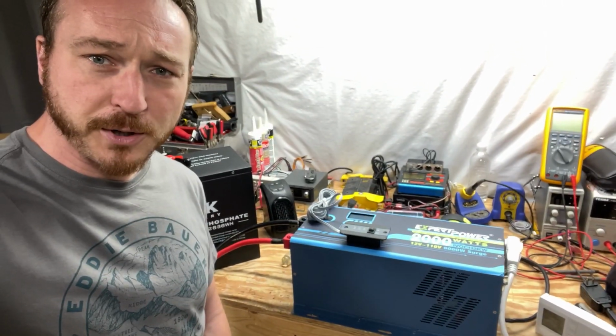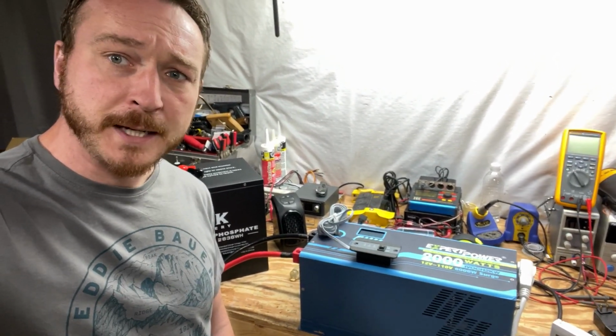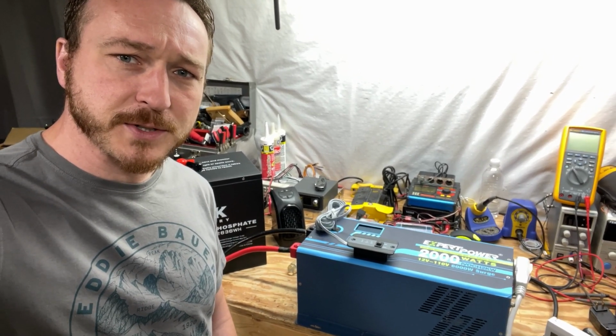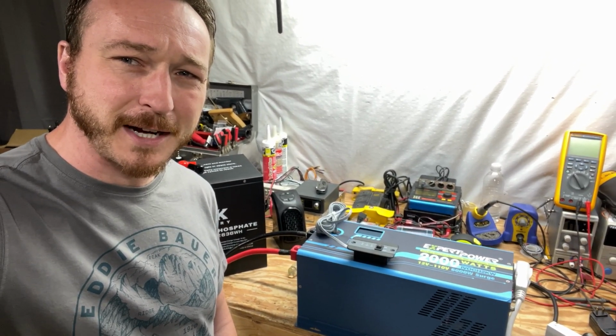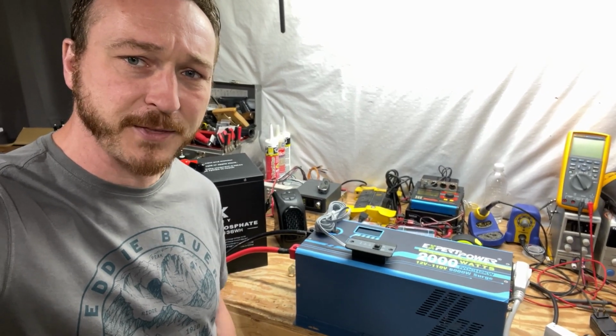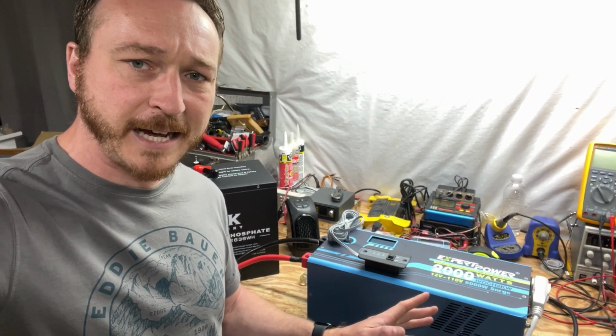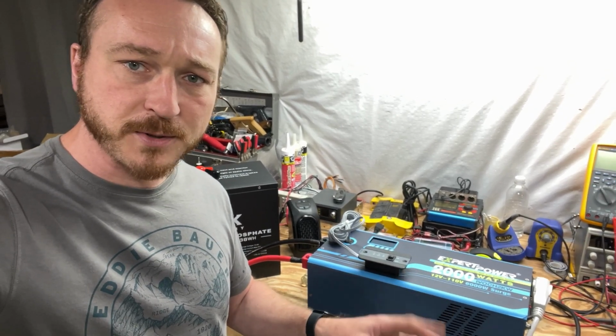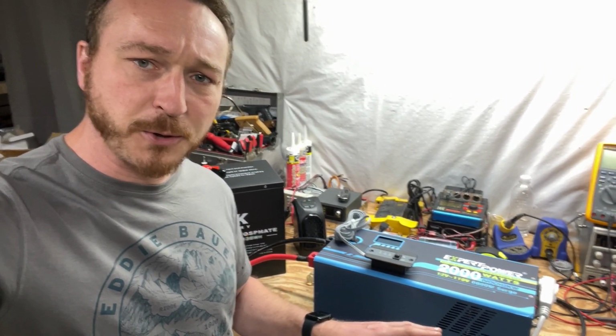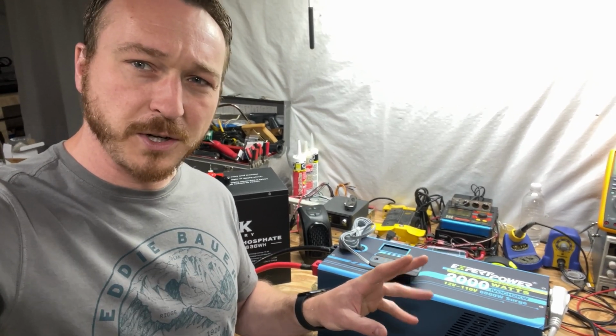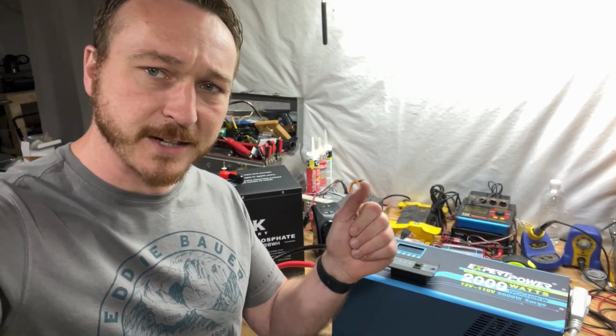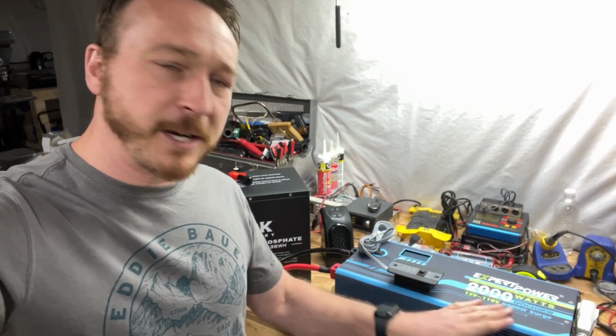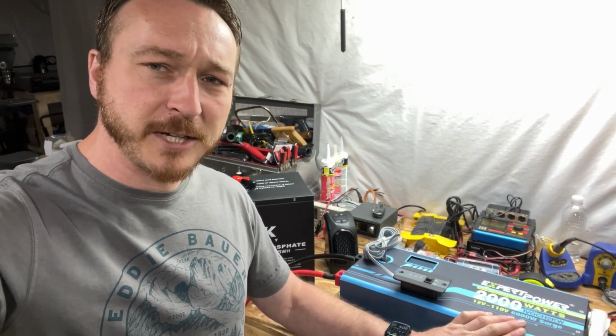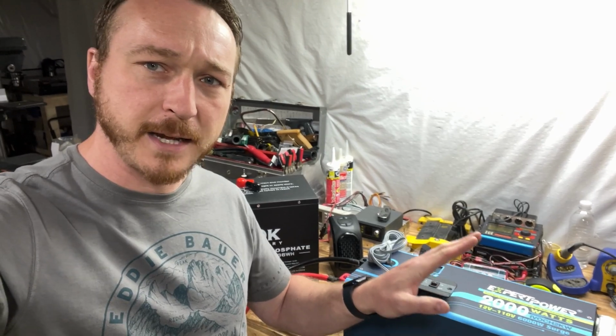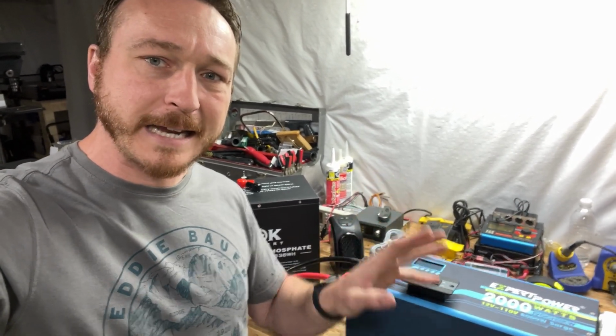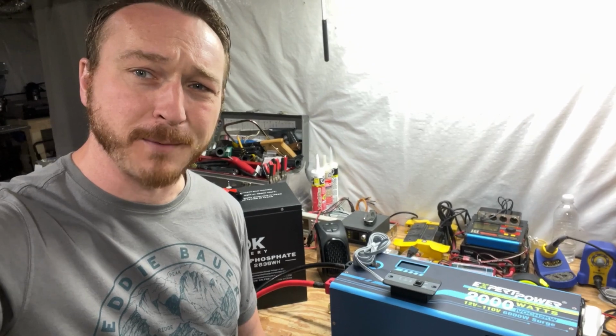I paid about 430 bucks for the Expertpower. It was used, and when it came I thought it was defective, but it was really just a hot neutral reverse on the onboard outlets. I fixed that fairly simply, swapped some cables around inside. The low frequency inverter was really buzzy under a very specific load that I usually use to test - it's actually like a heat gun. So I thought this was defective, but I've tested it with every other load at the same exact amp output and cannot reproduce that low frequency buzz.